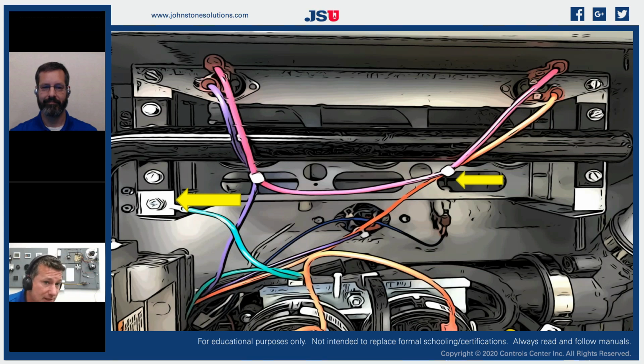So I've got an 80% Goodman furnace. I just ripped it all down, used all the factory wiring, put it on a broken AC pad that we had. And so that's my demo, right? That's a not fully operating furnace. We put the last control board we replaced on, everything worked right. I said, man, what's going on? I said, you got a bad ground. You have either a bad ground at the connection on the burner box, or you got a bad ground for your furnace, because we rely on that path of ground to flow our electrons.